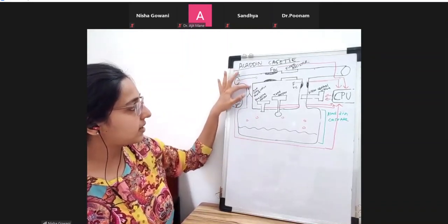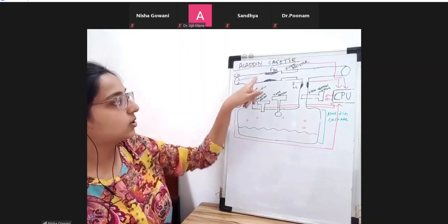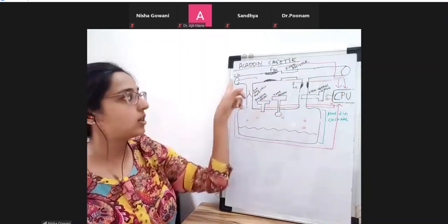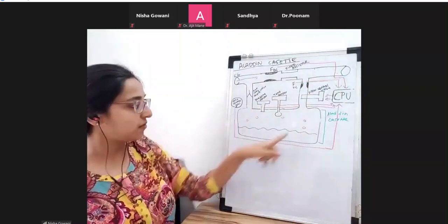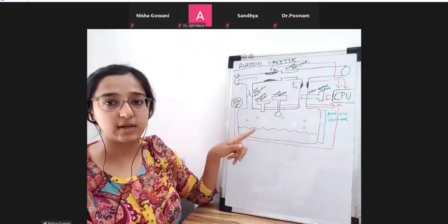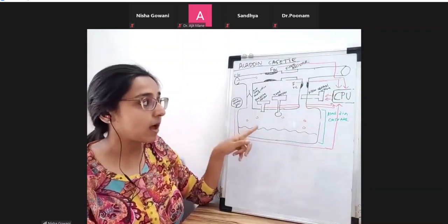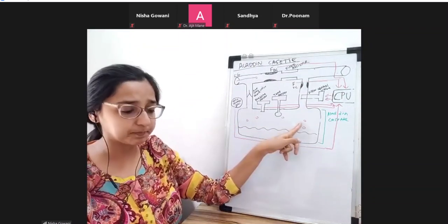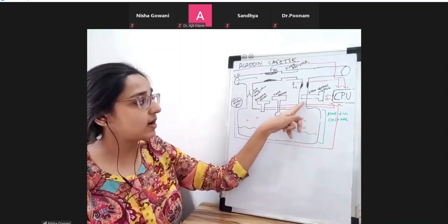So what will happen if it can't come in? All of the fresh gas will go through the bypass. No fresh gas is over here. What is over here? Only pure desflurane vapors, pure vapors. Now the pure vapors which are there will travel up through the flow.